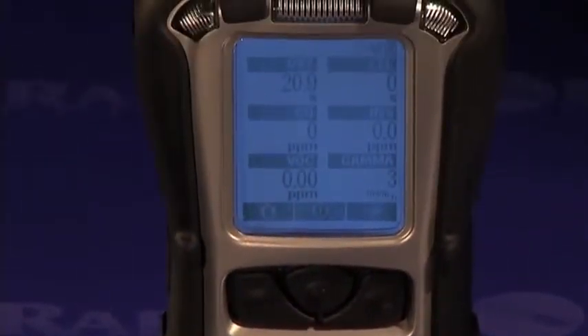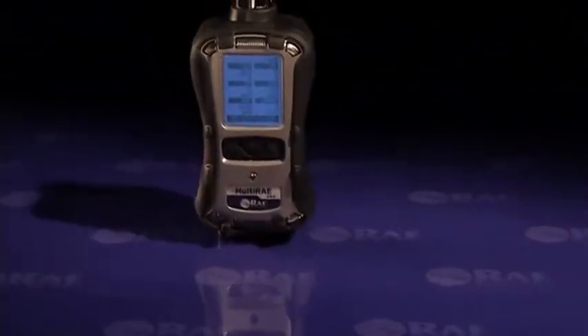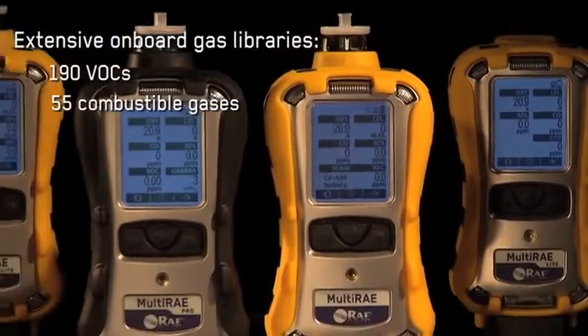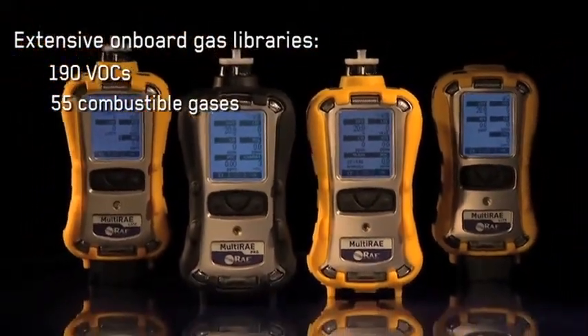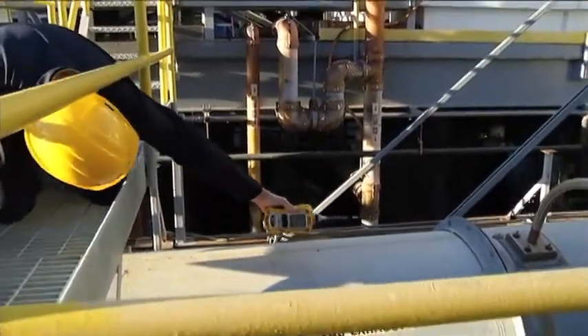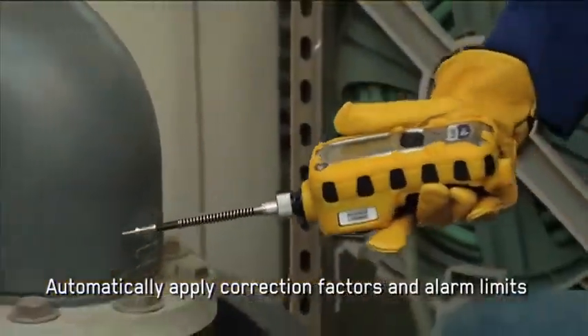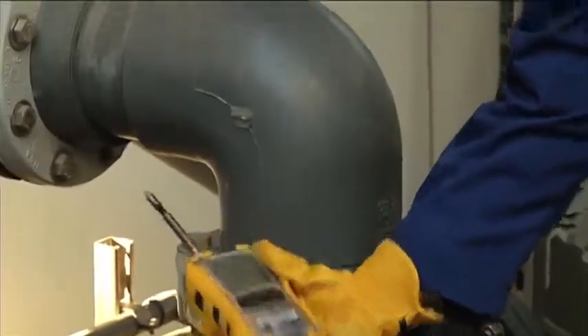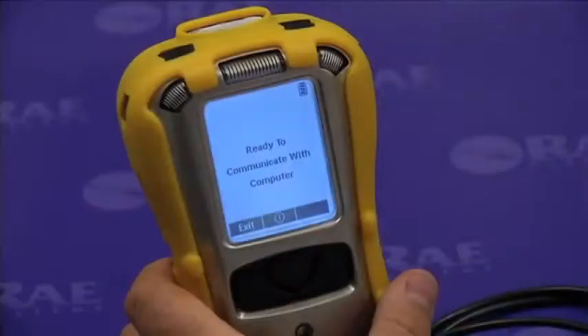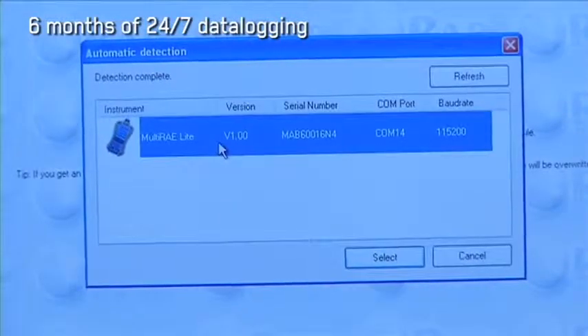Many MultiRAE users further customize their instruments by setting the measurement gases for the PID or catalytic LEL sensors to the compounds they encounter most often. The MultiRAE monitors have extensive onboard gas libraries for volatile organic compounds and combustible gases, so MultiRAE users can quickly configure the instrument to automatically apply the appropriate correction factors and alarm limits and produce readings in the equivalent units for the desired compound. For industrial hygiene applications, the instrument's extensive data logging capacity can store up to six months' worth of data taken at one-minute intervals for five sensors.